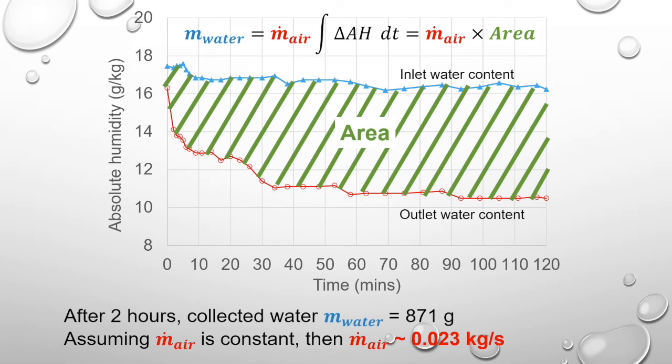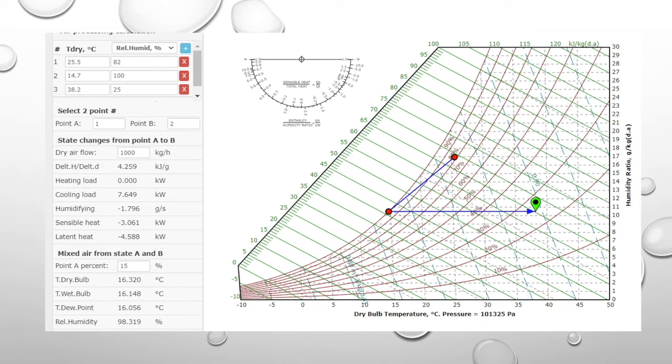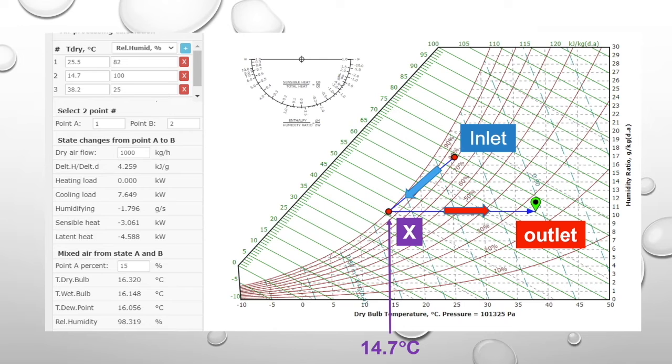The cooling capacity can now be estimated assuming that the dehumidifier first cools the air from the inlet to the dew point of the outlet, which is the state x here, then heats it to the outlet temperature. Here, state x has a temperature of 14.7 degrees Celsius. The cooling capacity is the air flow rate multiplied by the enthalpy difference between the inlet and state x.